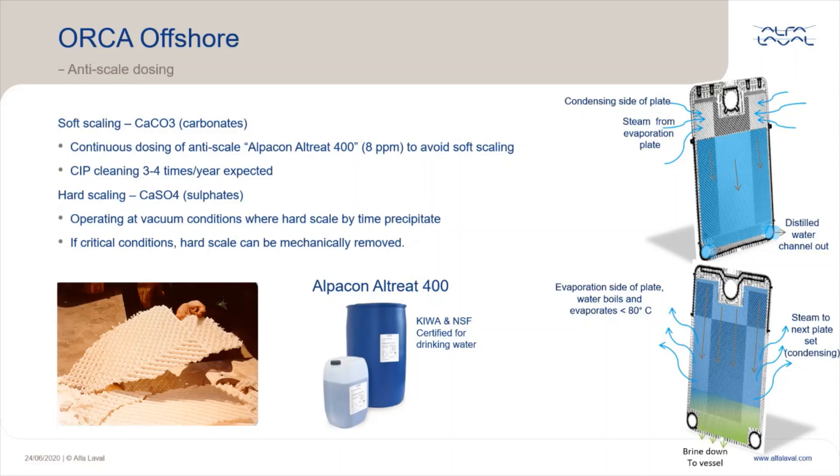A good thing with the plate heat exchanger used in all Alfa Laval freshwater generators is that they are easier to clean — both hard and soft scale — compared to a shell and tube heat exchanger, and the heat transfer surface can be returned to its original state. The use of anti-scale is strongly recommended; it makes a huge difference, so use it and check the dosage regularly. Alfa Laval recommends Alpacon Altreat 400, which is KIWA and NSF approved for drinking water. It is tested with proven efficiency at temperatures up to 85°C and brine concentrations according to Alfa Laval freshwater generator design. Benefits include lower operating costs, higher output, less maintenance hours, lower spare part consumption, and longer equipment lifetime.